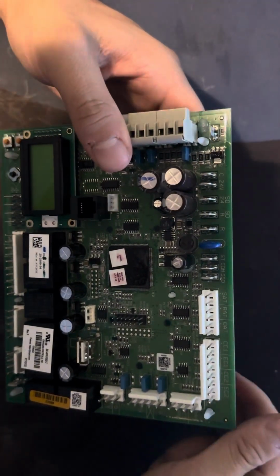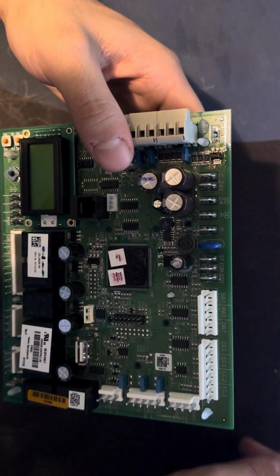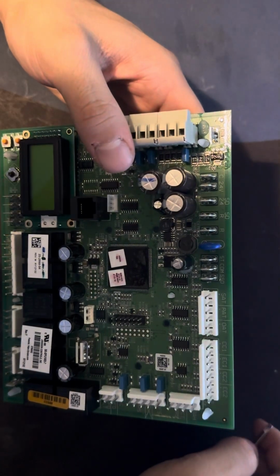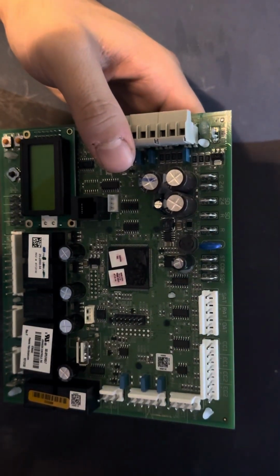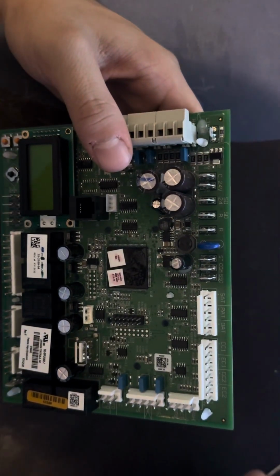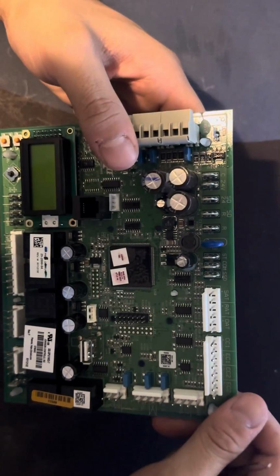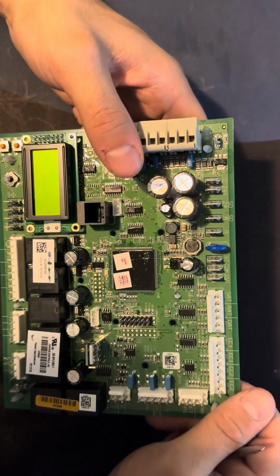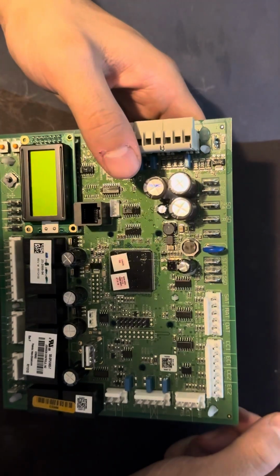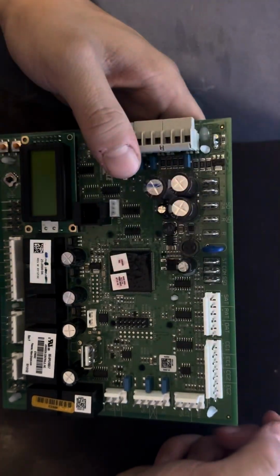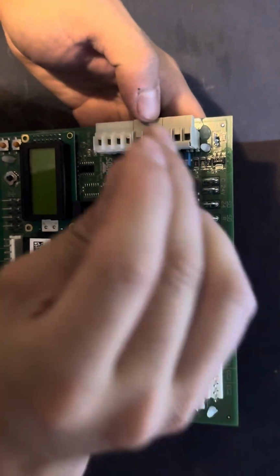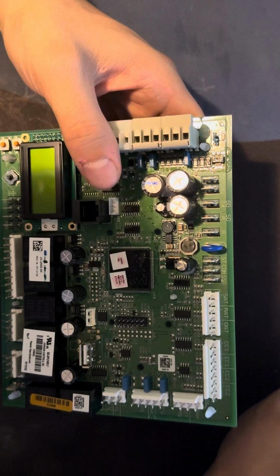All right, so now I want to talk about some common causes of why we usually see this HS1 off due to limit switch popping up on our screen. First one being, on 208/230 volt units, you've got to make sure that you're tapped into the right tap on the transformer. So if your incoming voltage is closer to 208, make sure you're tapped into 208. Closer to 240, tap into 240. That will definitely change your secondary voltage drastically.